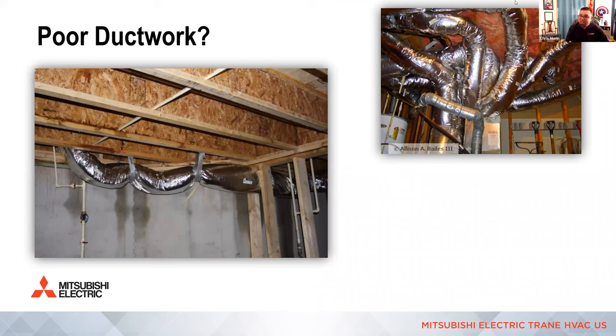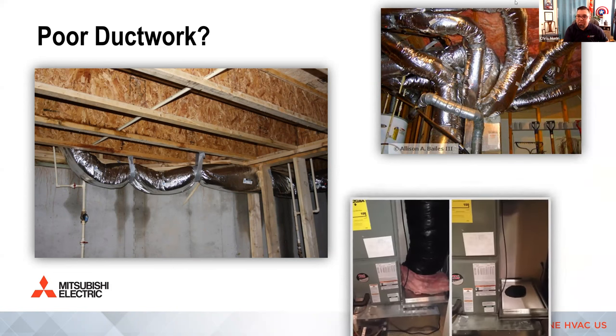You have to install a duct correctly. There's actually rules for flexible duct design as well. One of them is you actually have to hang it no further than 18 inches with solid hangers, right? You can't use tape to hang a flex duct.